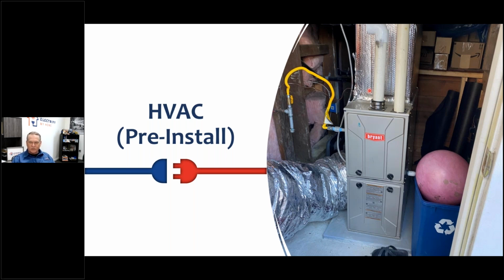This whole remodel was done just 4 years prior, so we knew the ductwork was in good condition. As a matter of fact, it tested out at 3 to 4% leakage when we were all done. Some of the ductwork came right off the plenum and served a room here and here. We also increased the size of the return, from a 12 by 24 to a 14 by 30, and used the proper type of grill, increasing the return air duct size to an 18-inch duct from a 14-inch duct.